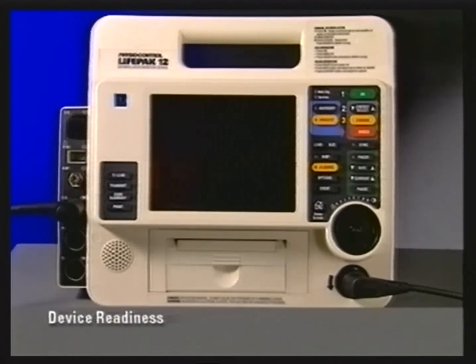Periodic inspection and testing of the Lifepak 12 defibrillator monitor helps to ensure that the defibrillator is ready for use at all times. An operator's checklist is provided in the operating instruction manual. It is a suggested checklist to inspect and test the defibrillator. It may be photocopied for your use. This checklist is not a replacement for preventive maintenance tests, which should be performed regularly by qualified service personnel.